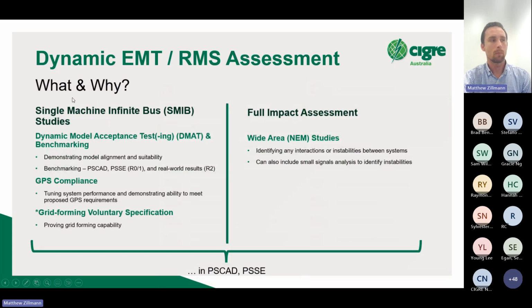Jumping into this in a little more detail - what are we doing and why? Usually when you're moving into dynamic EMT and RMS modeling, if you're early stage, you're probably doing dynamic model acceptance testing. AEMO have released a DMAT, which is effectively a standard set of benchmark tests that anyone can do on any model. You don't have to know where you're connecting to the network or the specifics - you could pick up models from a manufacturer and start running that today.